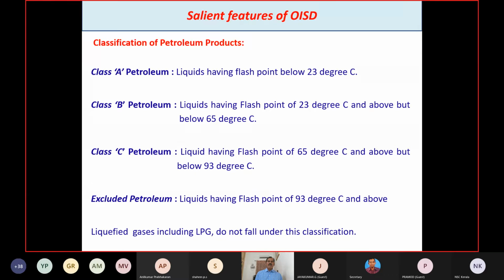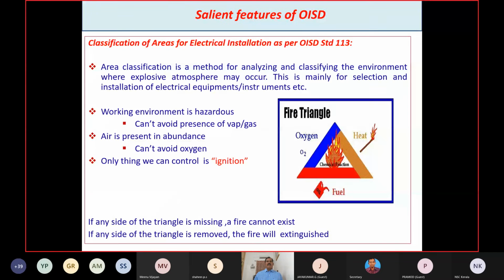And liquids having flash point of 93 degrees centigrade and above are categorized as excluded petroleum. Excluded petroleum, for example, furnace oil and bitumen, all come under excluded petroleum. And liquefied gases, including LPG, do not fall under this classification. That is a different classification. So the next standard we are taking for discussion is OISD standard 113, classification of area. This is mainly for selection and installation of electrical equipment and instruments inside the hazardous area. So area classification is the method of analyzing and classifying the environment where an explosive atmosphere may occur.